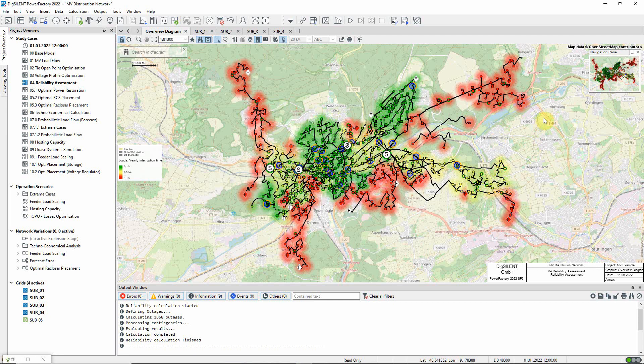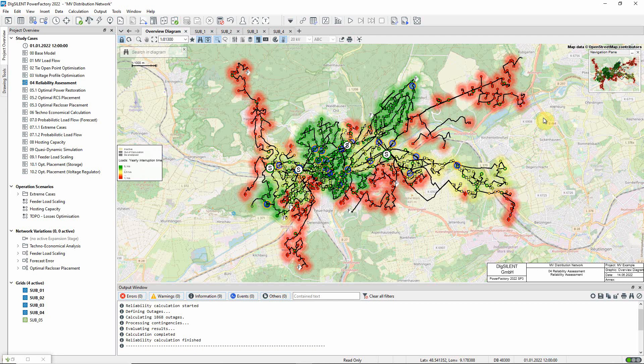It is coloured to indicate the annual interruption time, which is calculated for loads. The areas coloured red are likely to experience over one hour per year of interruption to supply, and it can be seen how the extremities of the network are weakest in this respect.